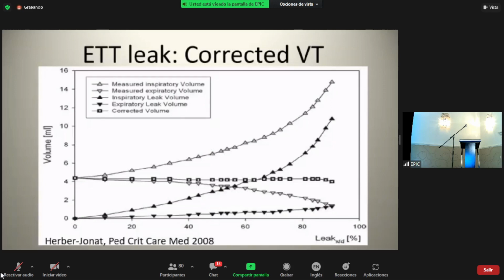Some ventilators have better leak compensation than others. This is just an illustration of the fact that tidal volume measurement becomes increasingly inaccurate as leak goes up from 0 to up to 80%. There is a feature on the Draeger ventilator that effectively compensates and will maintain that tidal volume calculation very close to reality, the set 4 ml, up until almost 80%.